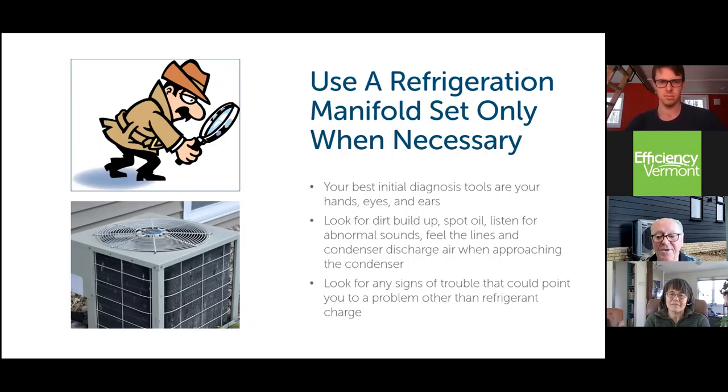Feel the lines and the condenser discharge air when approaching the condenser, just a sanity check. It's not going to be totally accurate. But if you walk up to a system and it's a hot summer day and you put your hand over the condenser fan and there's no heat coming out of there, you automatically know that you're in trouble.